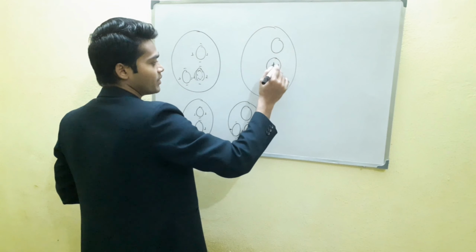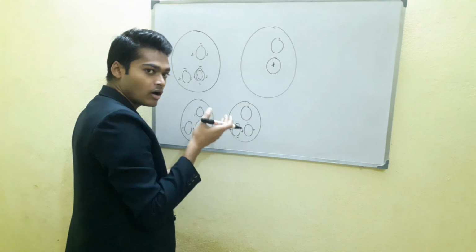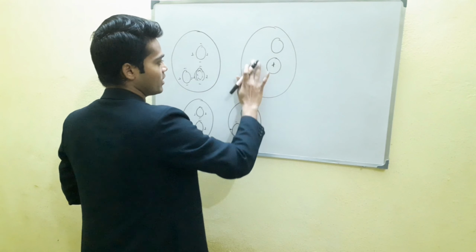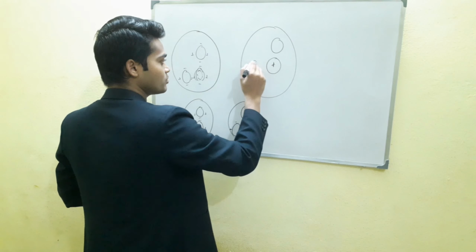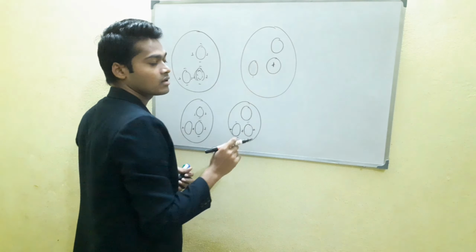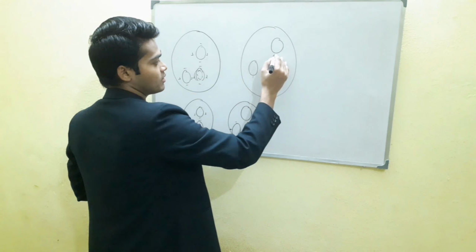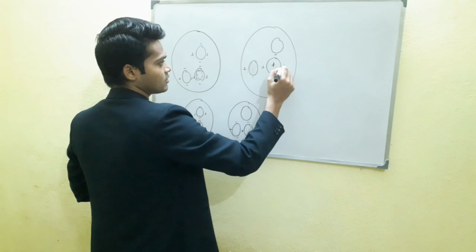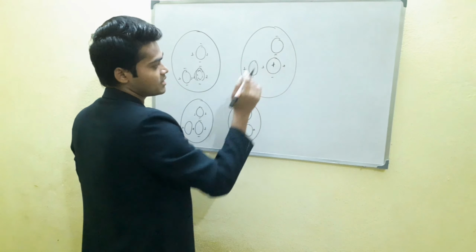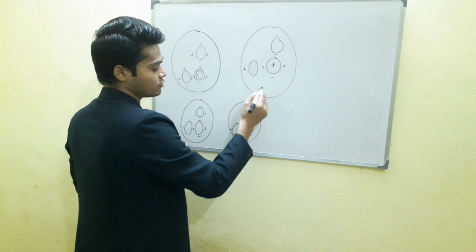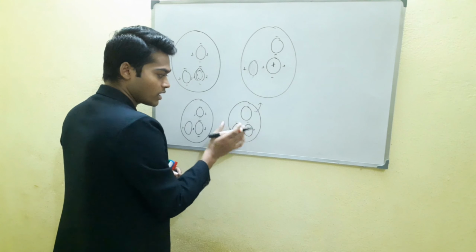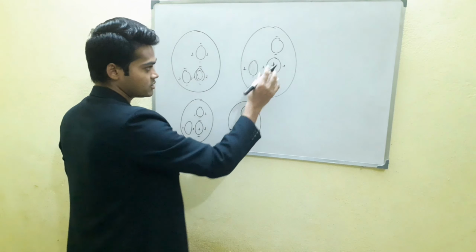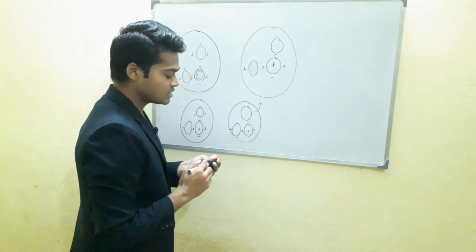here is an alignment which is already seen on the instrument, on the keratometer, right? We have seen this type of Mires, right? It means the central Mires must be over the plus sign, right? This is the actual scene. If you get this one, it means okay, but here the plus sign should be inside the central circle or central Mire, which means this is the exact position.